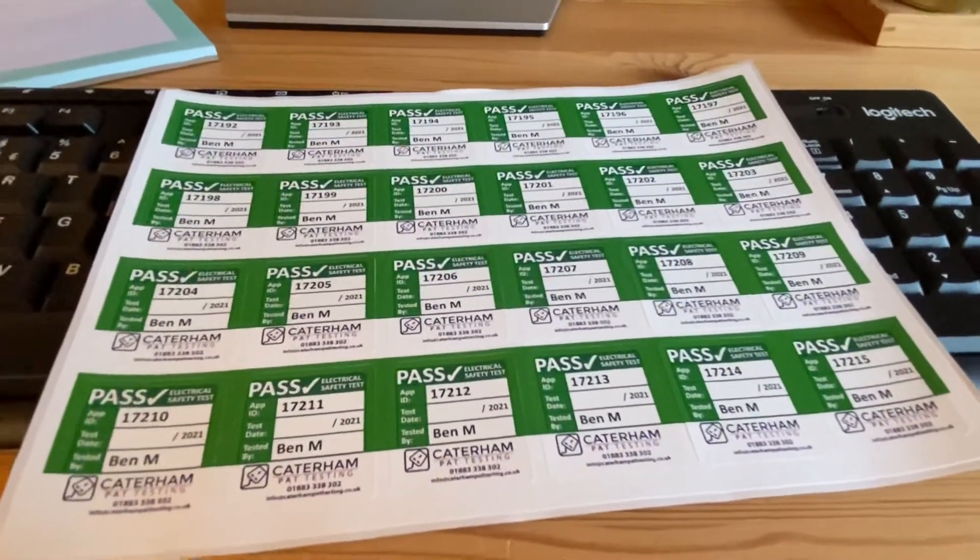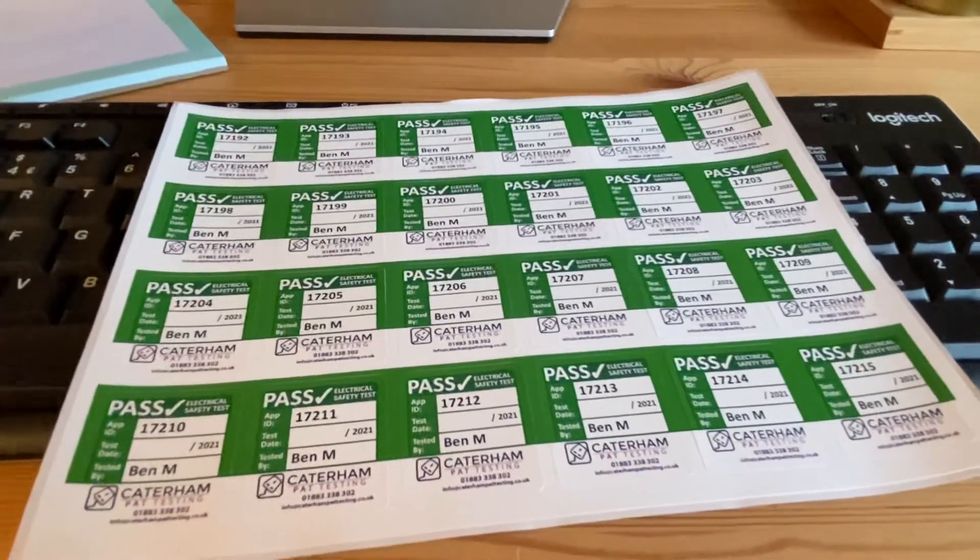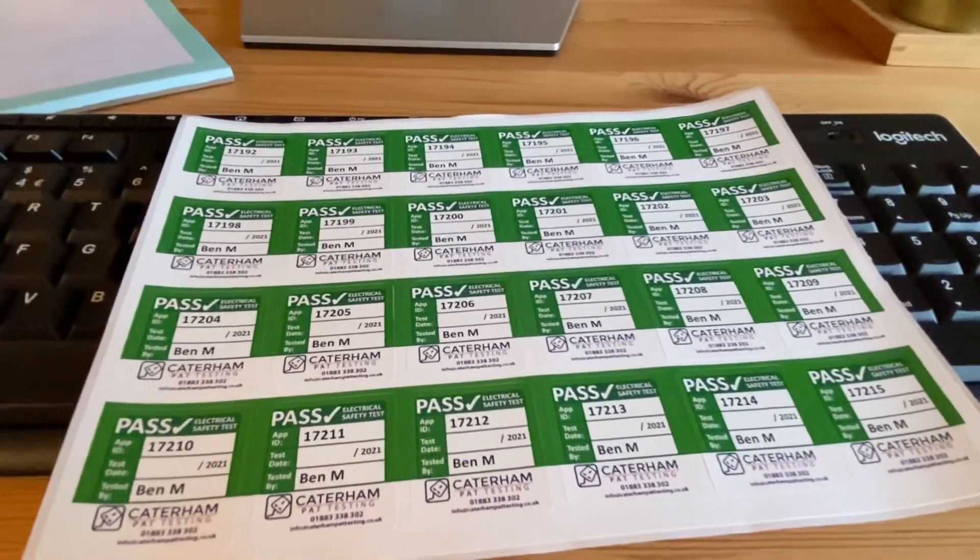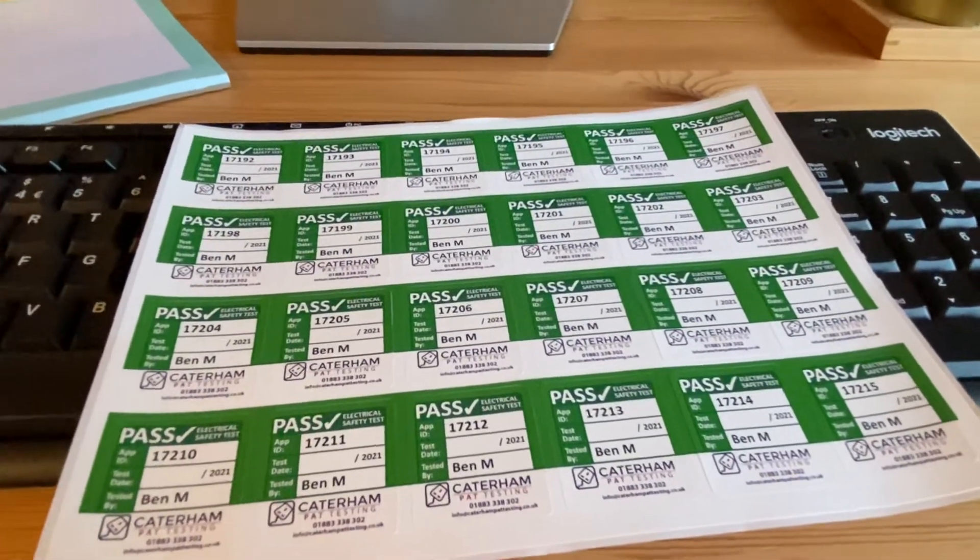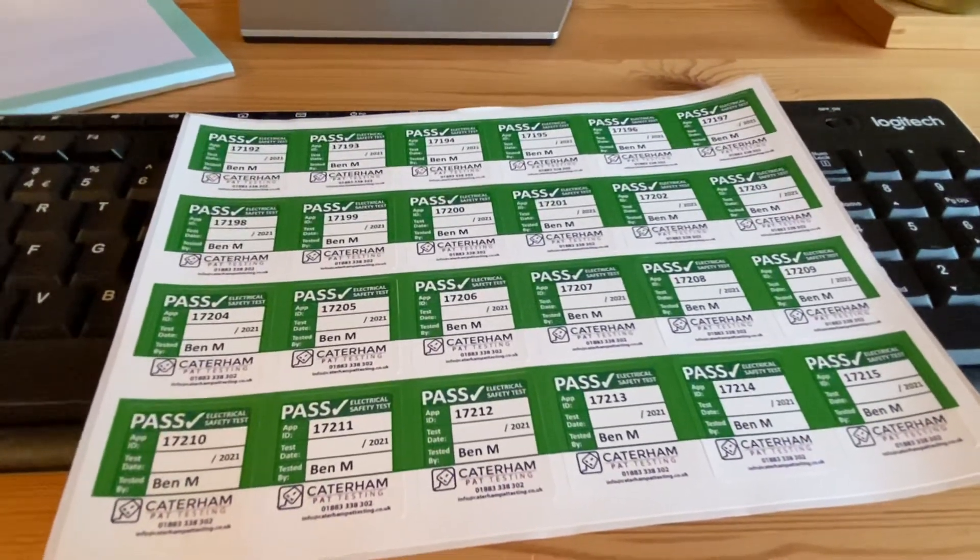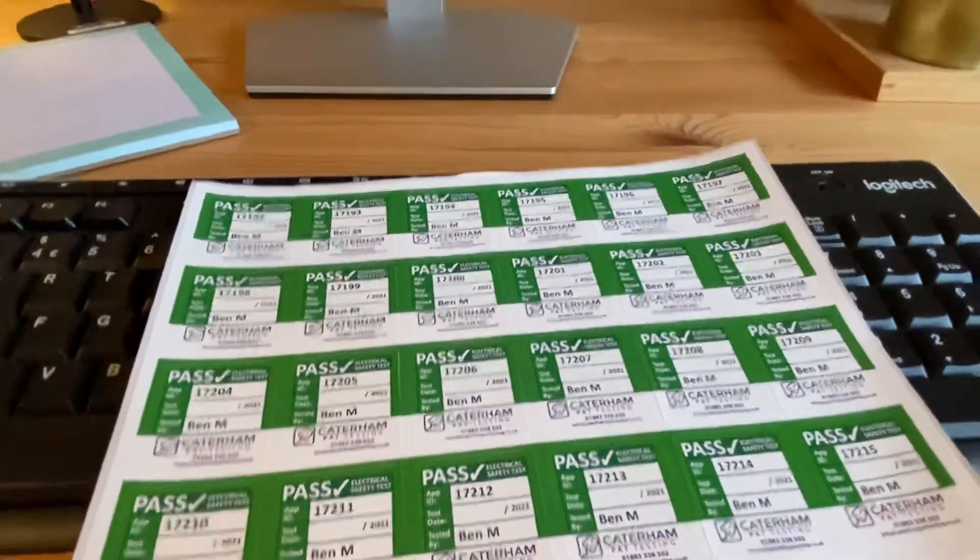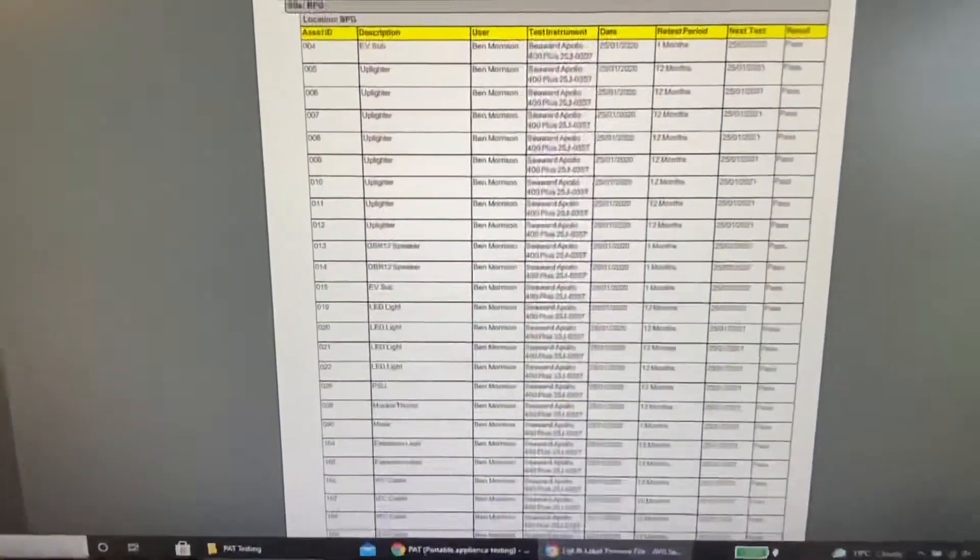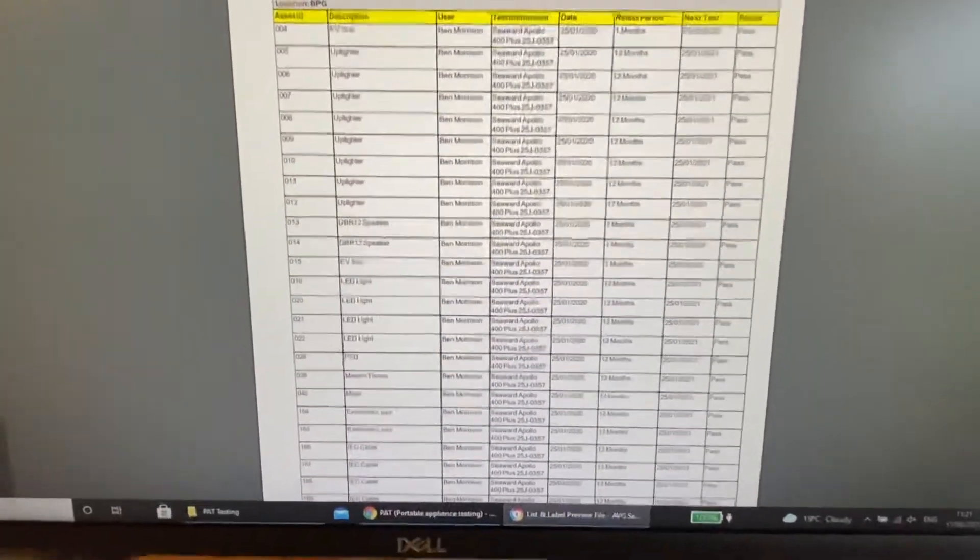So just important to say on your labels, your labels should only be giving the date it was tested and not a retest date. There's still some labels out there, they're called fourth edition labels, sorry third edition labels, where they have the retest date. But there is no requirement now. There's no need to put a retest date on the items because lots of different items have lots of different retest dates. So that's the concise list that we do here.